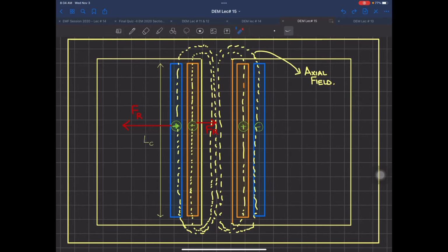The word used is bracing. Bracing means that you are actually going to put some metallic part, certainly not an insulator for the magnetic current, because we don't want magnetic flux in that. So you are going to put something over here, and something over here, so that the winding does not go out. Otherwise, if the short circuit current persists for some time, the transformer is going to explode, because the clearances which we have kept in the tank design are not that much. 40 mm, 60 mm, not more than that.